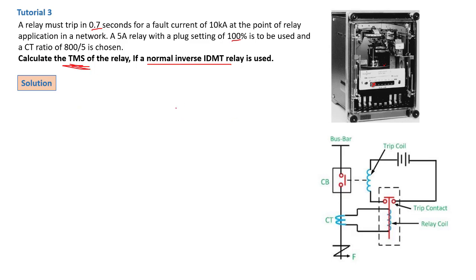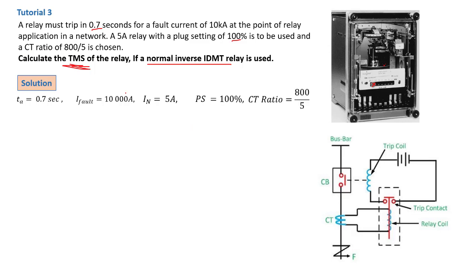It is important to establish the parameters we have. We have ta — the actual tripping time of 0.7 seconds. We have the fault current of 10 kilo-amps (10,000 amps), the nominal current for the CT secondary at 5 amps, plug settings at a tapping of 100, and a CT ratio chosen to be 800 over 5.